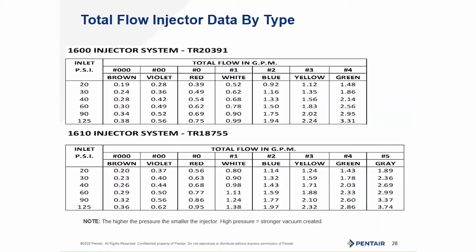Could you give a definition for nozzle and throat, and what's the difference between them? The nozzle itself is what creates the stream, a thin laminar flow stream that shoots down the throat, okay? And what that does is it shoots straight down the center of that throat where it doesn't touch the sides. And that's critical to a Venturi's operation. And that throat just acts as a channel.